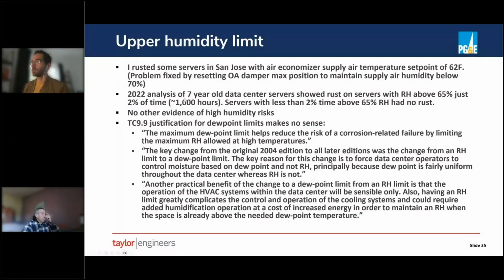We did an analysis of a data center that had been operating for years and basically came to a similar conclusion: if you're operating above 65%, even just 2% of the time, which is maybe 1,000 hours, you can have an issue, but as long as you stay less than 2% of the time above the 65, it wasn't an issue. So you can look at your annual weather data, do the calculations pretty quickly, and see how often you're going to be above 65%. There's no other evidence of high humidity risks that we've seen in terms of equipment failures or so forth. If others have information or data that they come across, please share it.